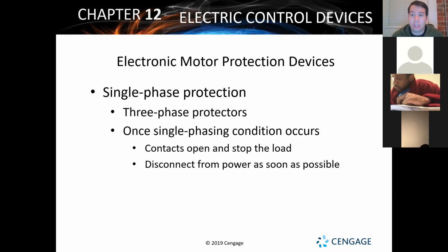So if electricity gets a little out of whack, if that rhythm gets messed up, then the system will shut itself down and will wait until it can fix the problem or have the three phases returned to the system, so that it doesn't keep firing up and sends the same voltage into a motor all at once, all on the same sides, or on all sides of it, and then it'll make this kind of sound that just goes, and that's it.